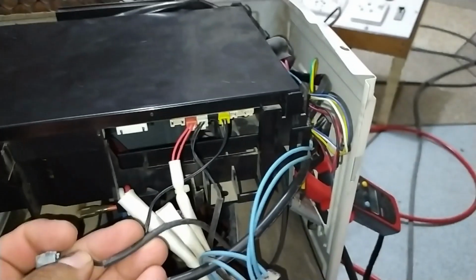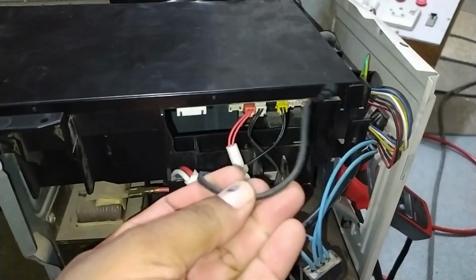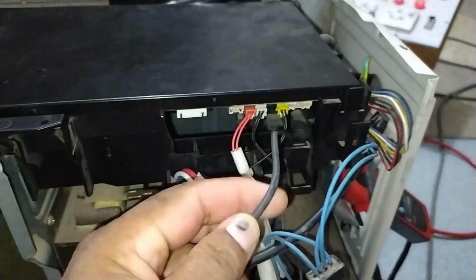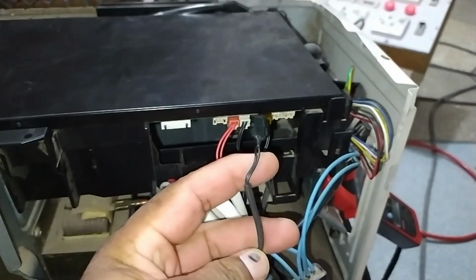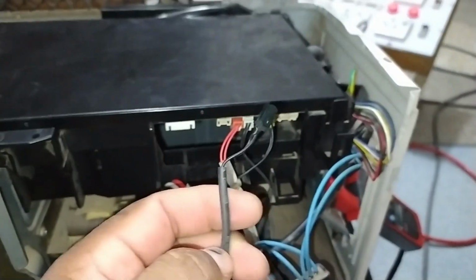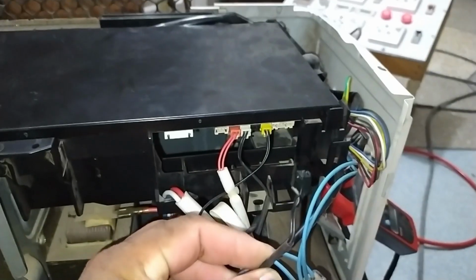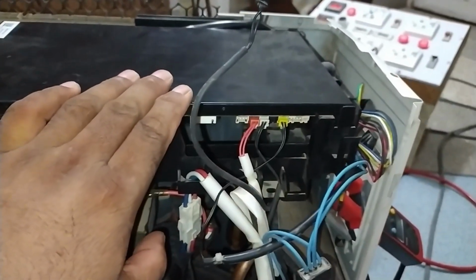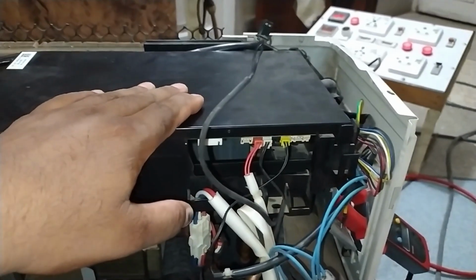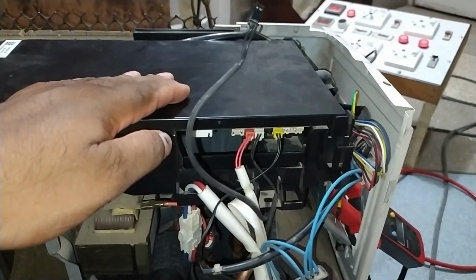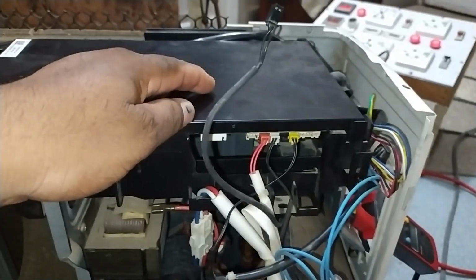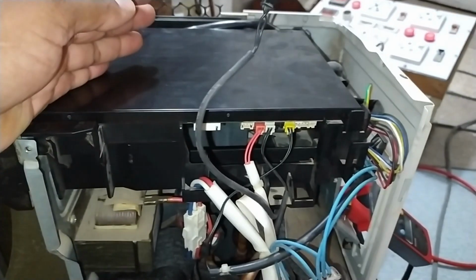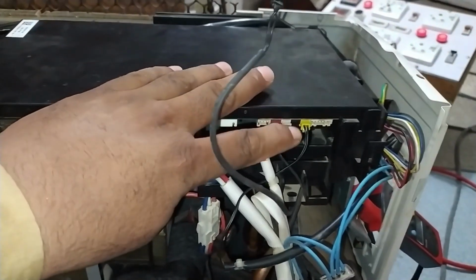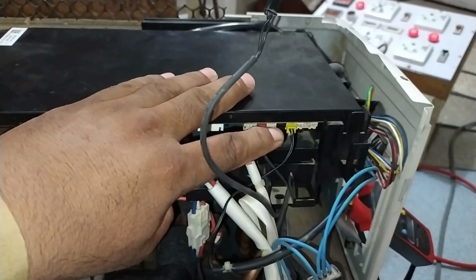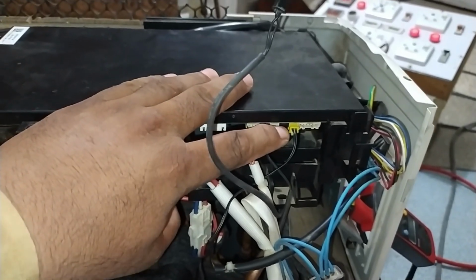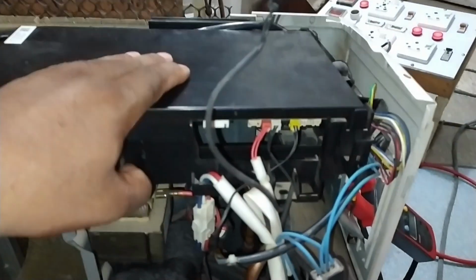This sensor is the condenser pipe sensor, also known as the heat exchanger sensor. If this sensor is damaged, has a loose connection, or gets short-circuited, the system will display error 1 on the indoor display. Additionally, if the PCB itself develops a fault, it can also cause error 1. This is because the PCB provides 5 volts to the sensor, which is necessary for proper operation. To troubleshoot, you should check whether the 5-volt supply is present on the PCB. If it is missing, the PCB may need repair to resolve the issue.